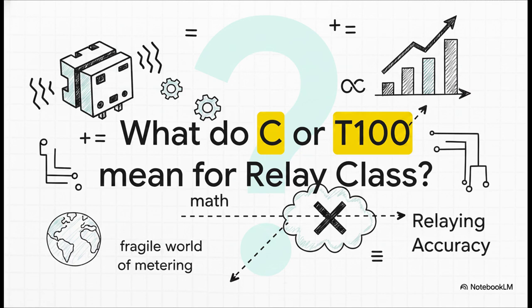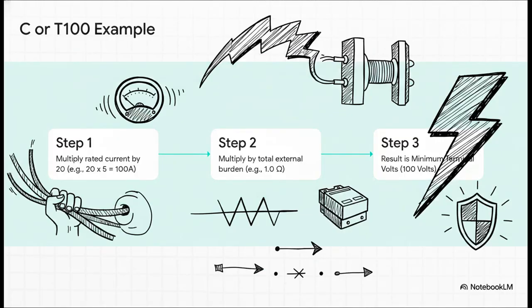So, if that's the somewhat fragile world of metering, let's pivot over to relaying accuracy. You'll often see protection specifications listed on a datasheet as something like C100 or T200. But what do these actually mean in the real world? Let's cut right through the confusion of these specific IEEE protection specs and just do the math. Okay, so that letter and number combination simply designates the minimum secondary terminal volts a CT can produce.